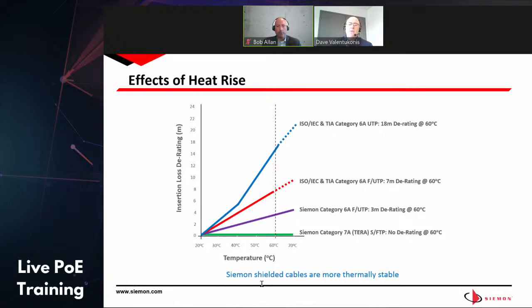If you bring it down to a category 6A shielded system, that drops significantly from an 18 meter reduction to a 7 meter reduction—much more manageable if you know how to design your telecommunications rooms and distribute your cable plant to stay within that overall 93 meter channel. We actually have some properties within our Siemon category 6A F/UTP cable construction that limit that derating to only 3 meters, so now you can have up to a 97 meter channel even in the worst case scenario.